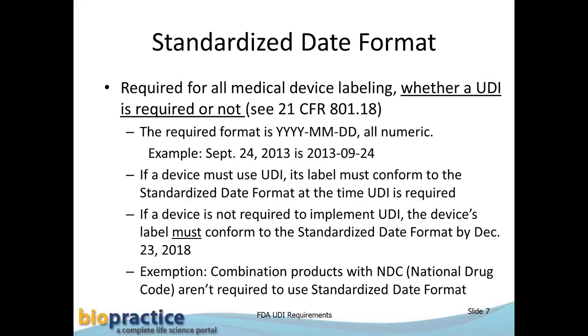What's this thing called a standardized date format? Sometimes this gets lost in all the commotion around the UDI requirements, but it was put into place at the same time as the UDI regulations were. Standardized date format is required for all medical device labels and labeling, whether a UDI is required or not. And I've put the CFR citation there, 801.18, that talks about standardized date formats.